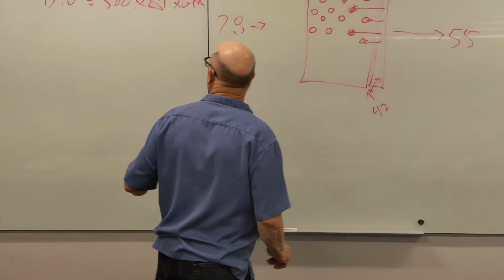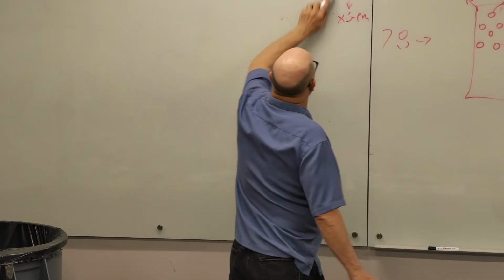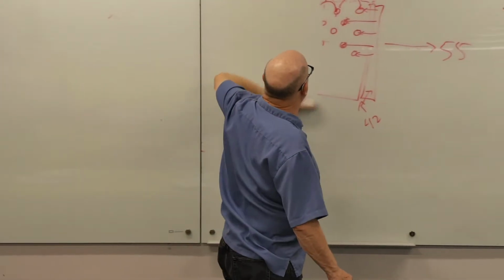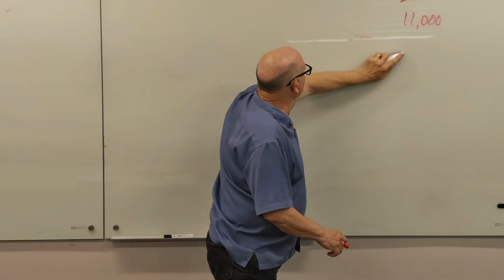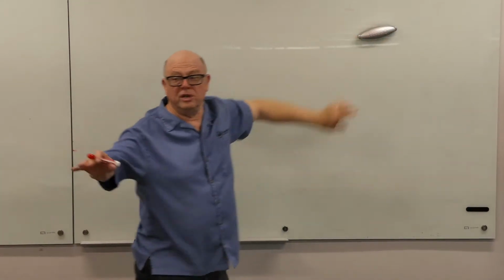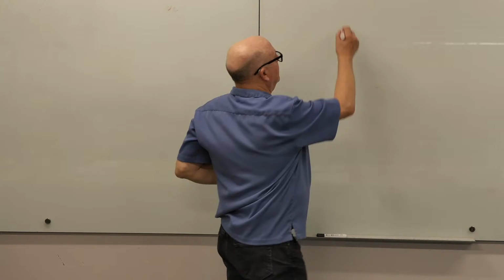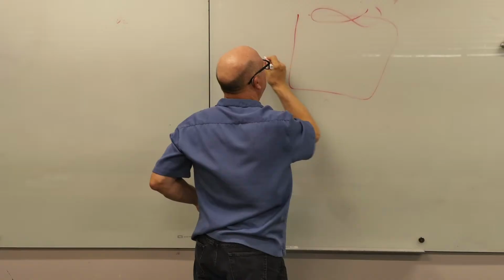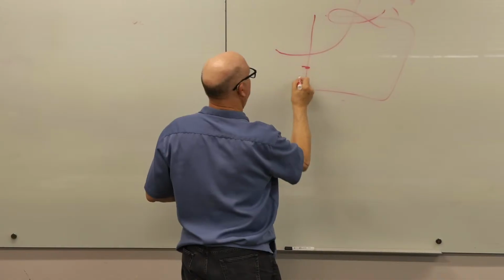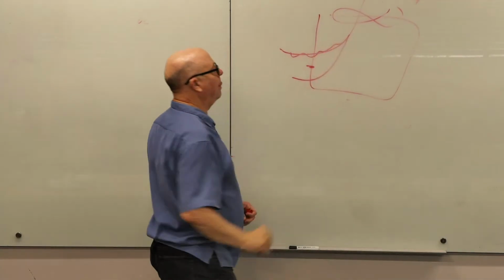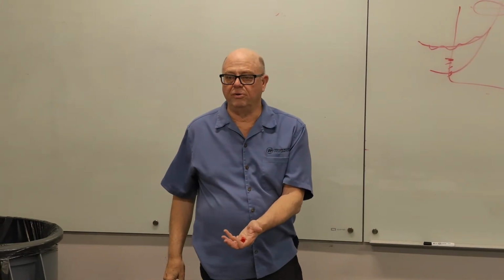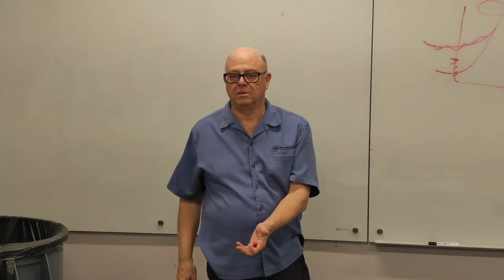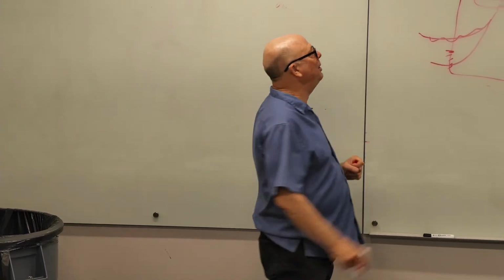Last point I was going to make is that counterflow is not limited to a coil. It's always counterflow with any heat exchanger, and let's take a cooling tower. If I've got a cooling tower with a propeller on the top, it's pulling air out of the, actually, typically it's pulling it from way down here. So forget that. Got some louvers here. How's the water being introduced? Somebody say from the top. From the top. Thank you.